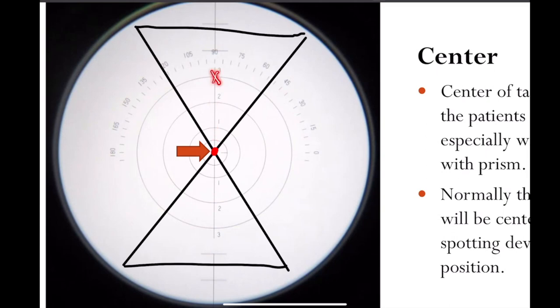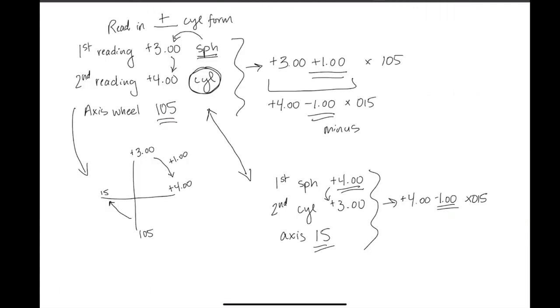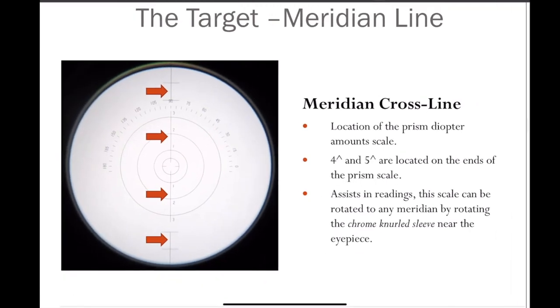So if we were here at three diopters base up, or three diopters base down — if they crossed here, one diopter base down. This meridian line here in the lensometer is rotatable, and you do that with that chrome knurled sleeve by rotating it right here. You can rotate this prism meridian line. The one, two, and three written on here are attached to this line. Right now it's aligned with the 90th meridian. When you rotate it along the 180, those numbers will go there. You could rotate them to 45, and your one, two, and three will be right along there. This is just to help you when it comes to prism.